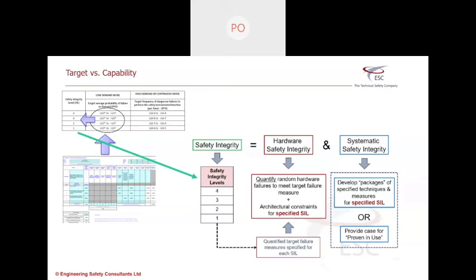It also includes validation against specification. So, we said we needed something to close that gap. We've engineered it. We've installed it. Before we use it, it would be nice to go and say, right, looking at what I needed as a specification, have I achieved that? And if I've achieved that, I have a level of assurance that it's going to do what I need it to do. If I haven't achieved that, what decisions do I need to make? Very seldomly, that decision is about a probability of failure on demand not meeting a target. And even more rarely, that at that point of validating, the PFD is the biggest concern.